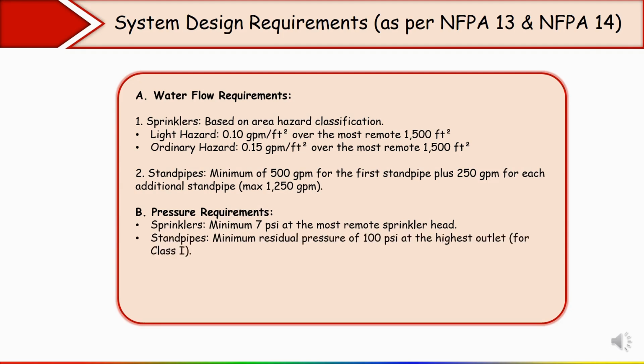Next, standpipe. Here in a standpipe, a minimum residual pressure of 100 psi at the highest outlet for class first is needed. Residual pressure means the pressure acting at a point in a system when flow is being delivered. So based on the classes of standpipe, for class first standpipe, minimum 100, maximum 175 psi. For class second standpipe, minimum 65 psi, maximum 100. For combined system, 100 psi minimum, maximum 175. Okay, so remember this point.